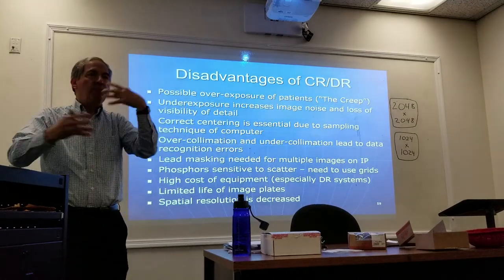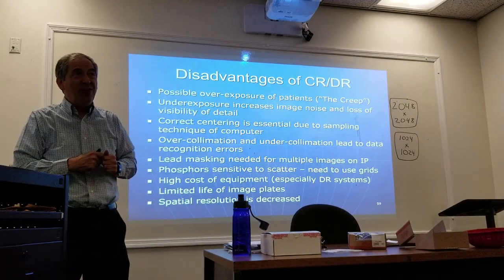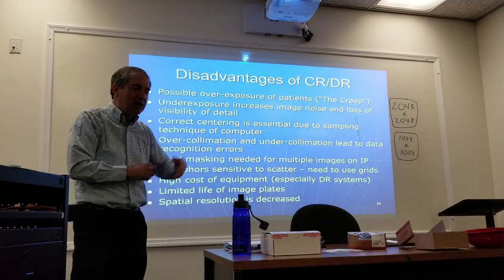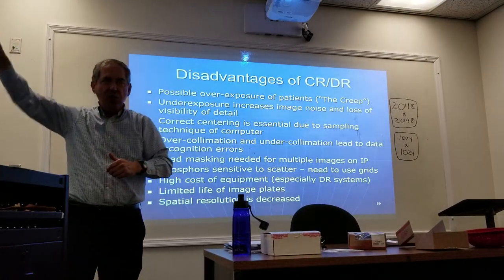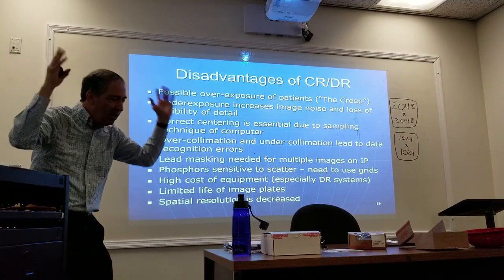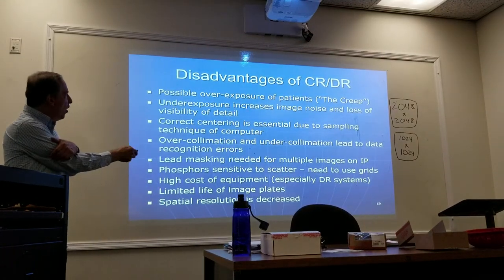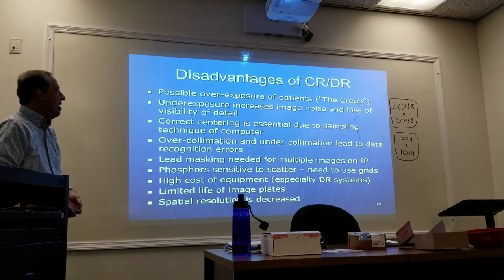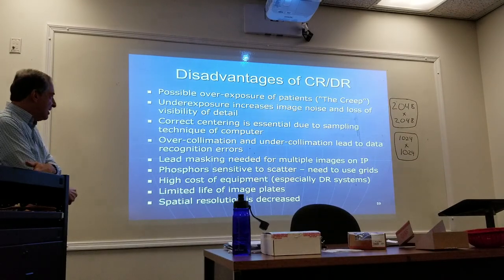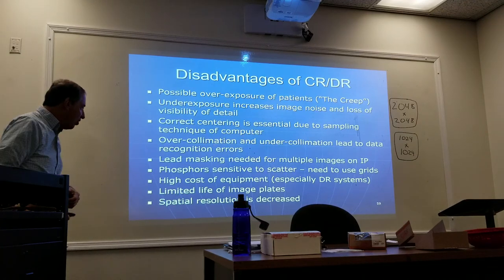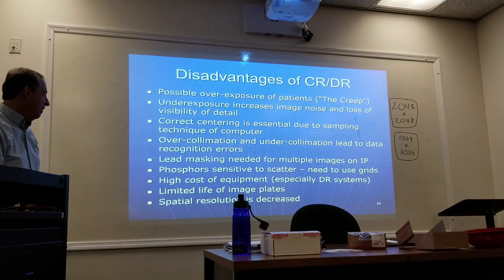Disadvantages include possible overexposure of patients — called dose creep. They thought the more sensitive photostimulable phosphors would reduce dose, but in practice technologists tended to expose higher to get better images, increasing patient dose. Also, if you underexpose, you get noise and loss of detail. Centering is now even more critical because you're doing sampling. Spatial resolution is slightly decreased compared to film.